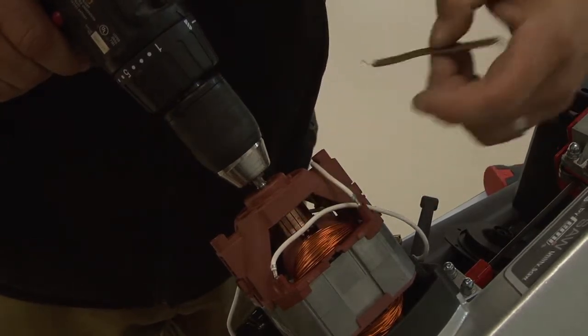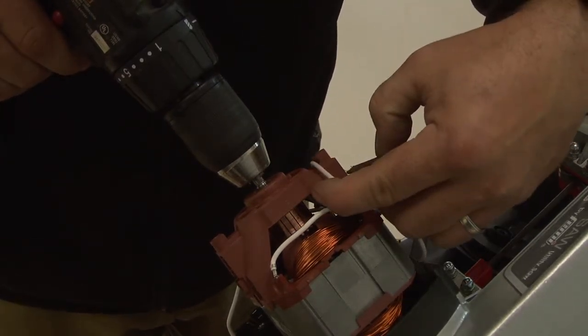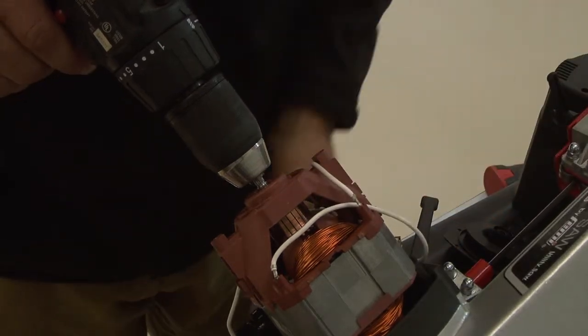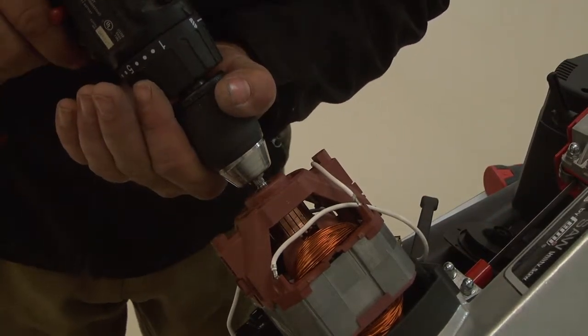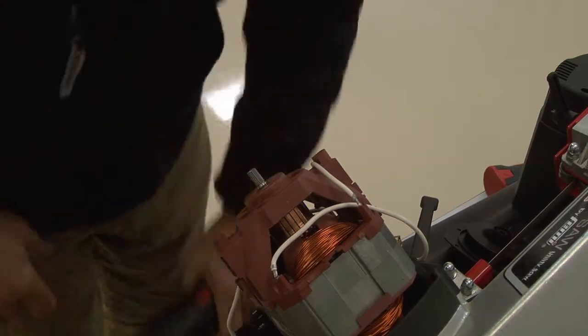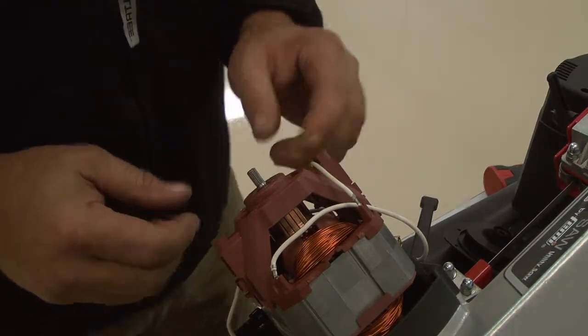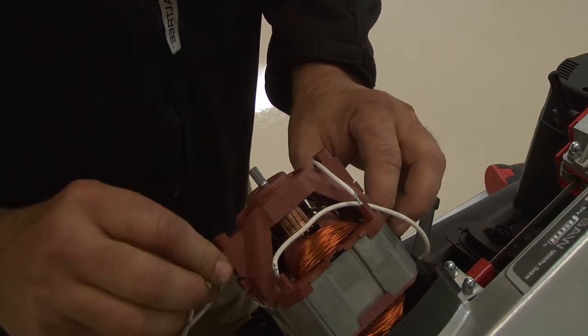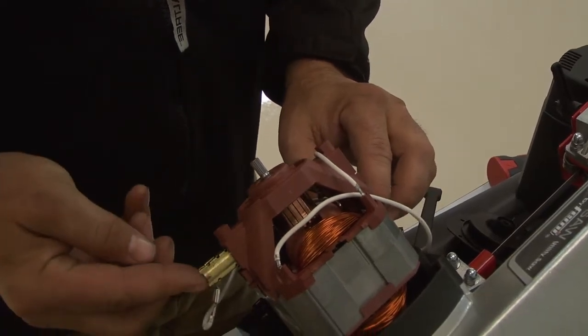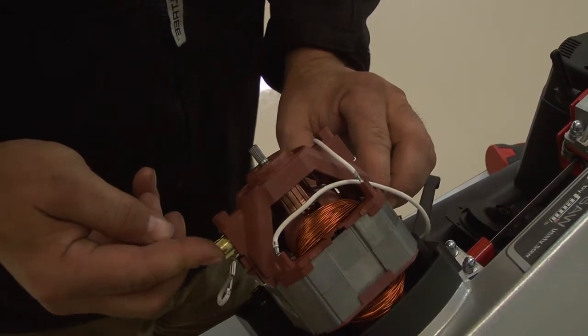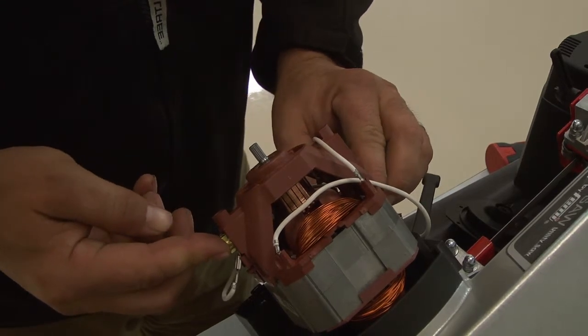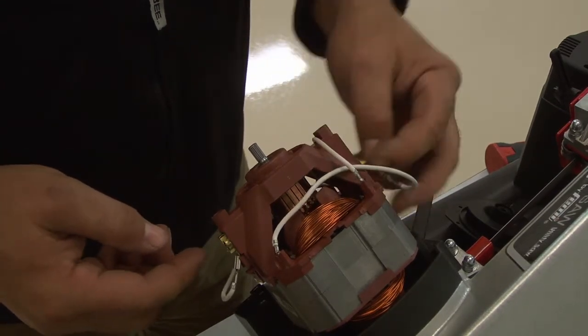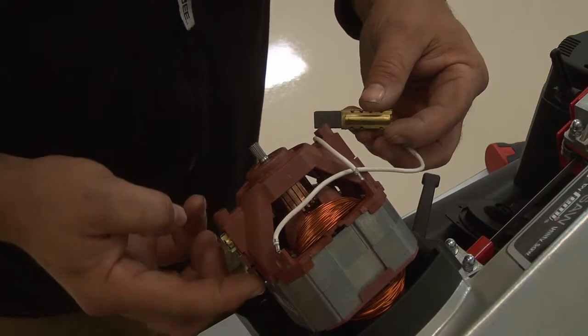It is not necessary to clean the commutator until it is perfectly shiny, but the black glaze should be noticeably removed. When the copper surface on the commutator appears to be substantially cleaner, the motor brushes can be reinstalled by pressing each one in until there is a slight click, and then press the wire leads back against the motor housing.